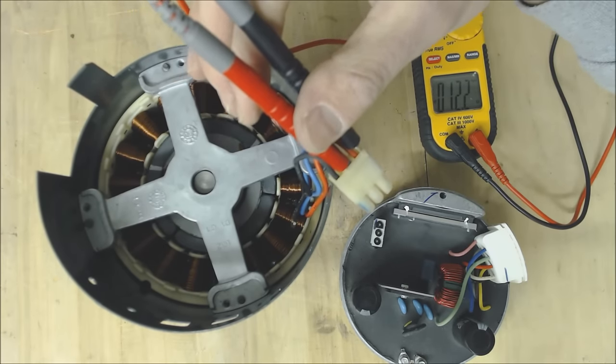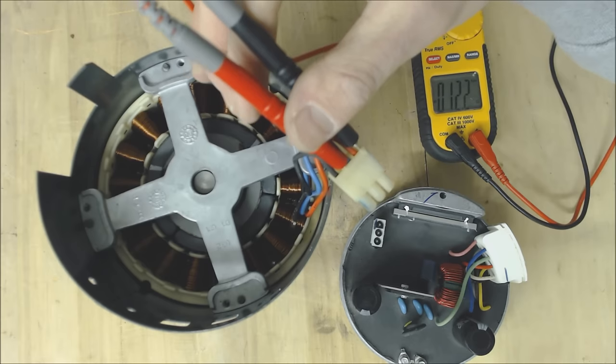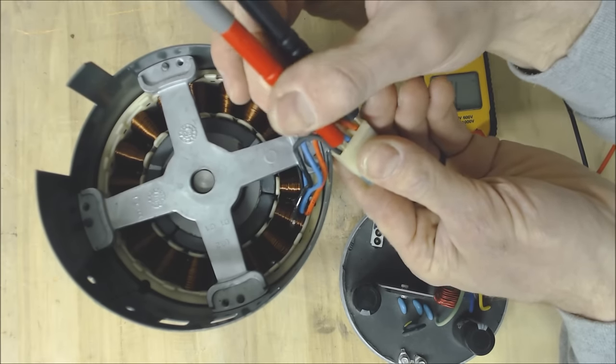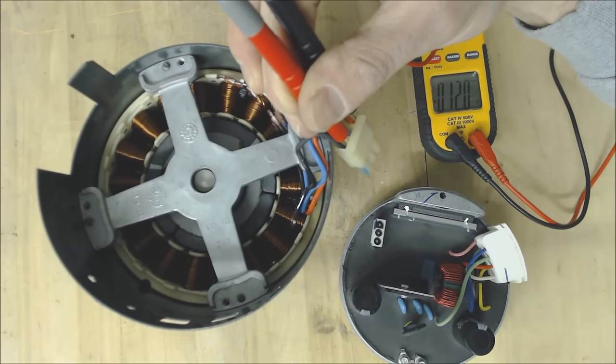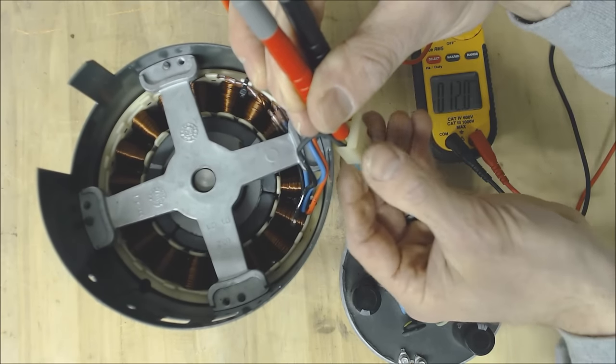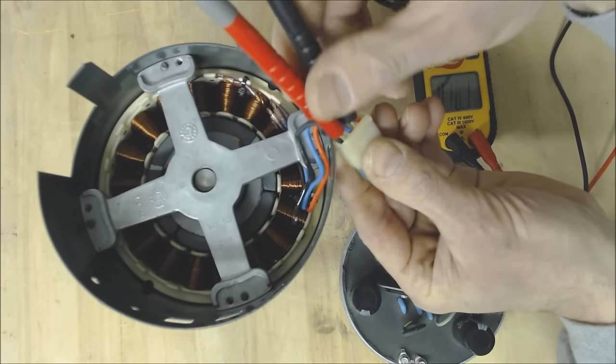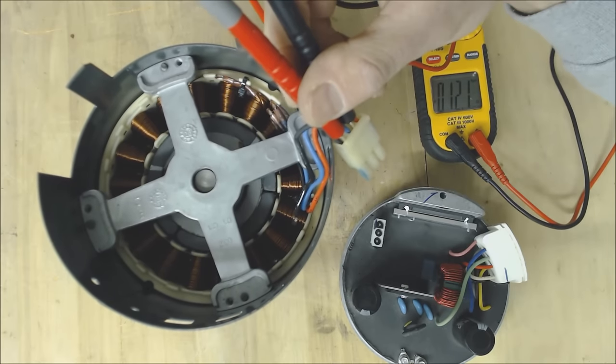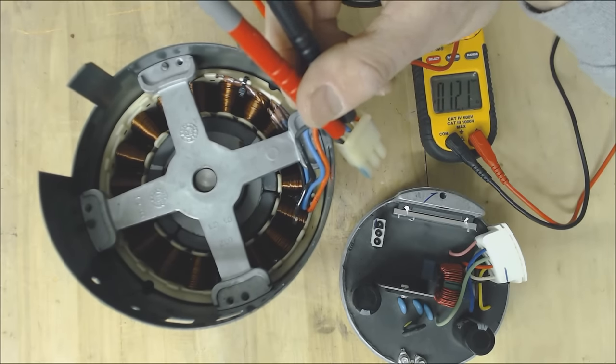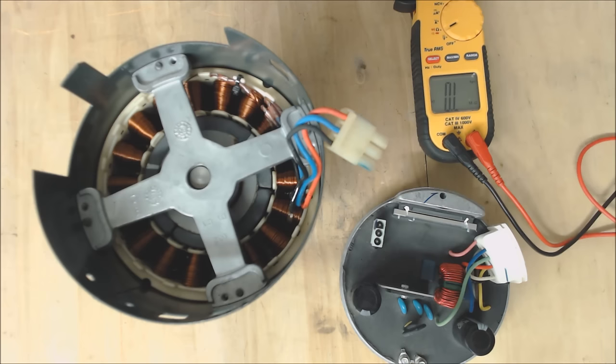You see that we're reading 12.2 ohms then you're going to take the other wire right there, about 12 ohms, right and 12.1 ohms so those are matching.